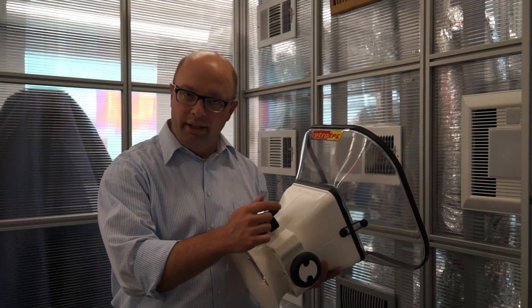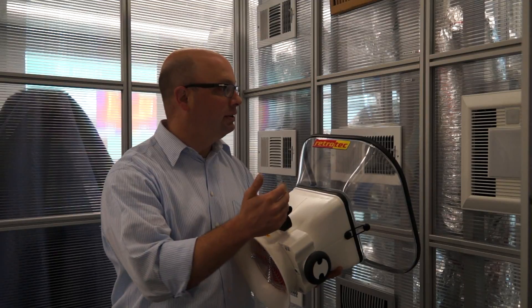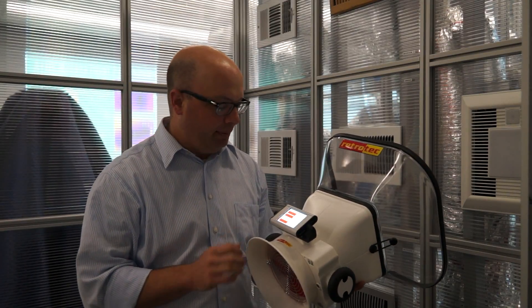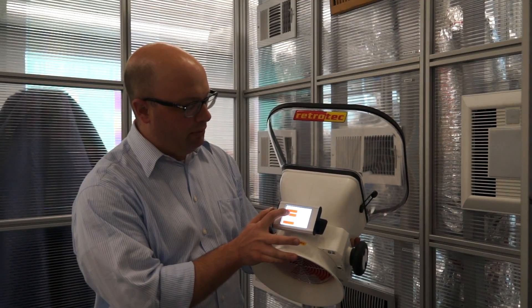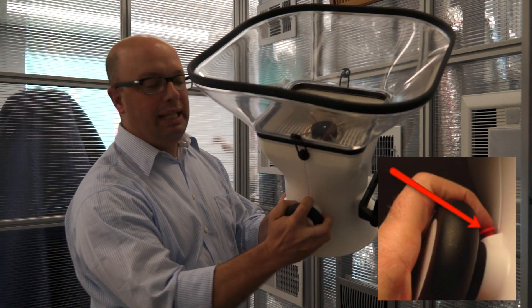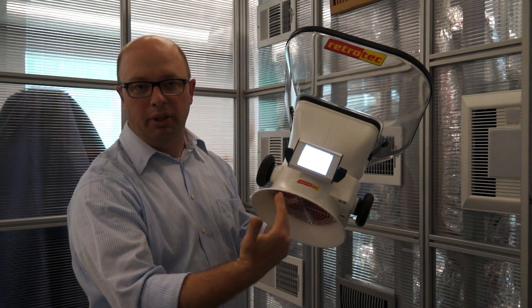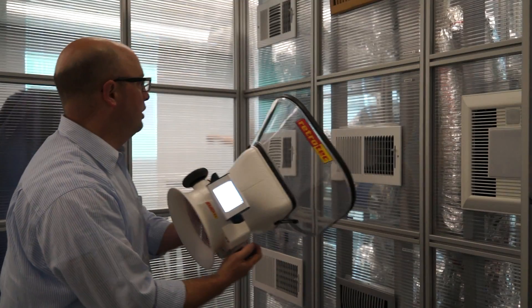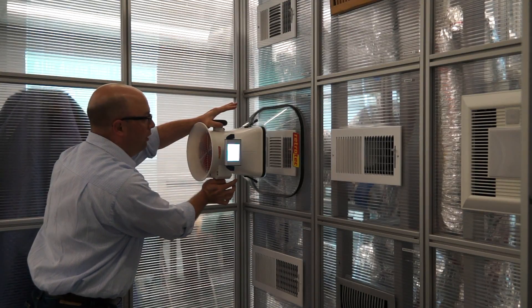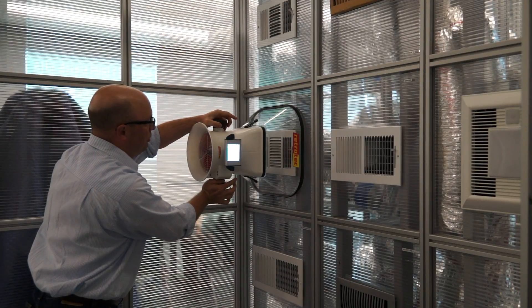We're going to now do some validation of the airflow coming from each one of these. We'll start using the Retrotec Flow Finder Powered Flow Hood to validate the CFM coming out of each register into each room before adjusting any of the dampers to bring our system into balance. We'll set our system to validate, and on the left-hand side there's a red button that begins the process of the power flow compensating for the pressure it's getting from the supply. Let's start here with the kitchen — make sure it's firmly placed up against the wall or ceiling wherever your vent is, then press the red button.